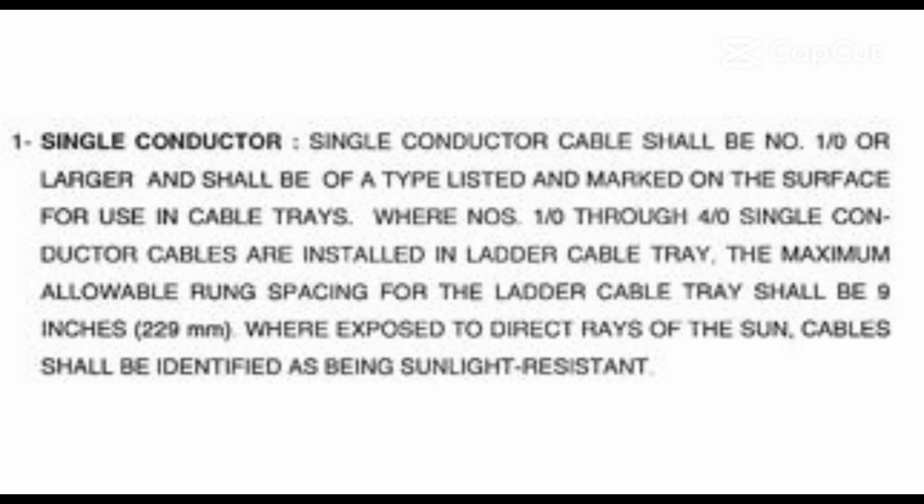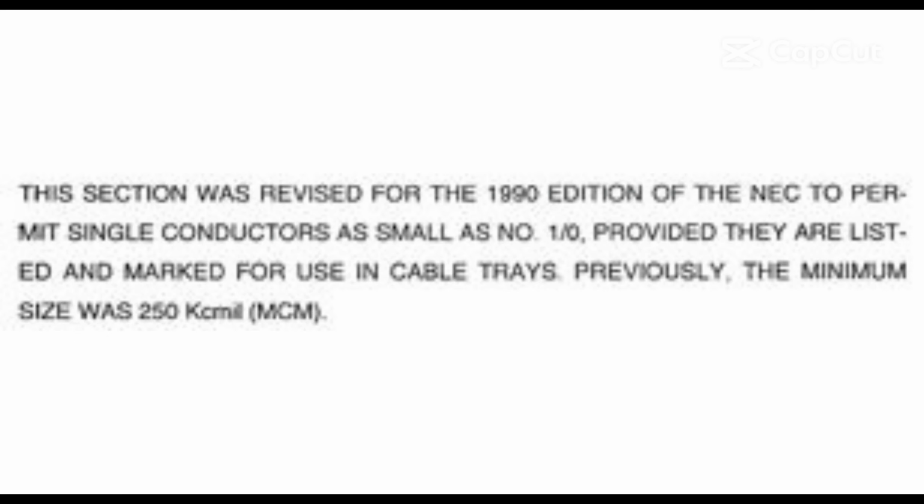1. Single conductor. Single conductor cable shall be 1/0 or larger and shall be of type listed and marked on the surface for use in cable trays. Where 1/0 through 4/0 single conductor cables are installed in ladder cable tray, the maximum allowable rung spacing for the ladder cable tray shall be 9 inches 229 millimeters. Where exposed to direct rays of the sun, cables shall be identified as being sunlight resistant.